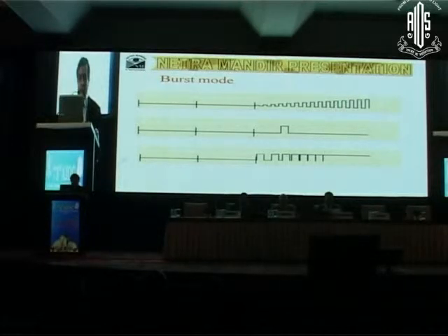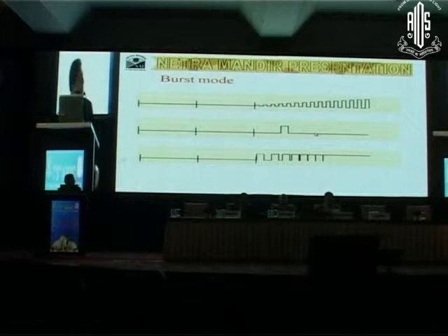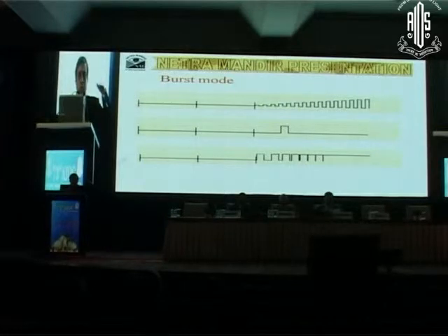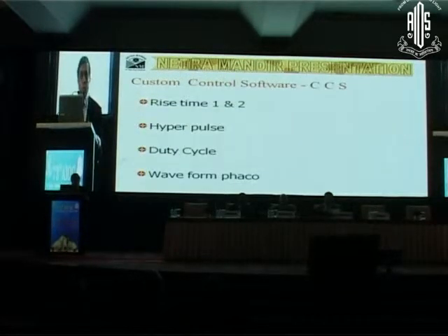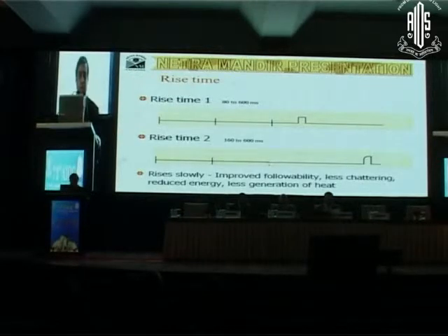And as you can see in the lower graph, when you depress the foot pedal, unlike the pulse mode which you see in the first upper graph, the energy increases here because there is a full delivery of the energy. As you depress the foot pedal, what will increase is the frequency of the burst, until it goes to the continuous mode. Then we came up with a couple of other advances like rise time 1 and 2.